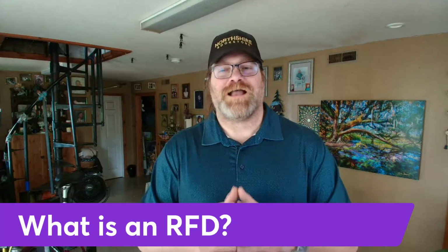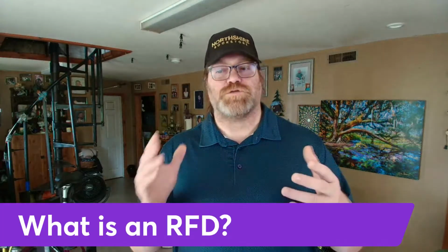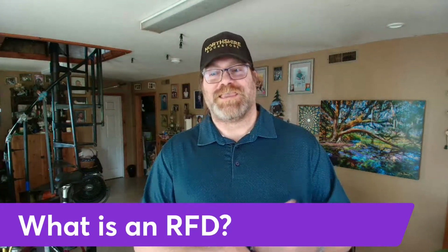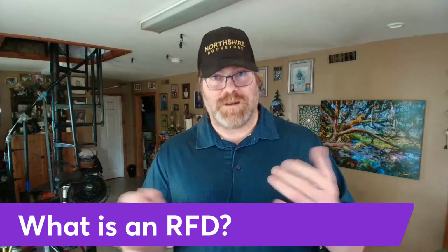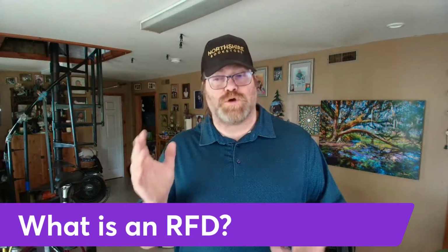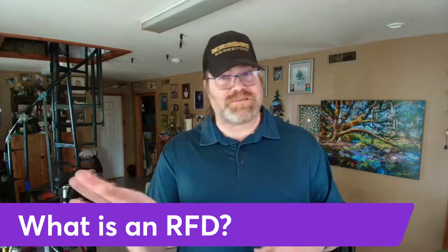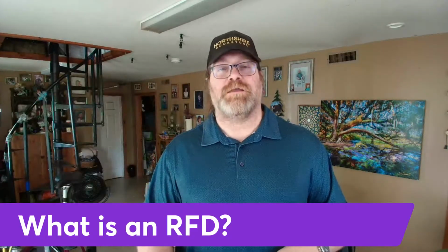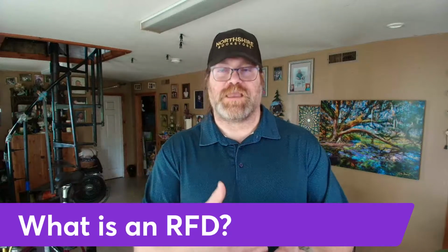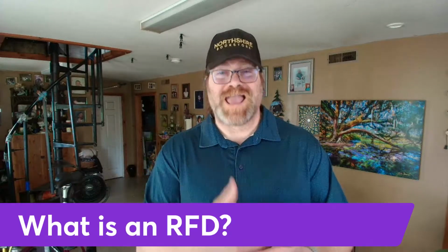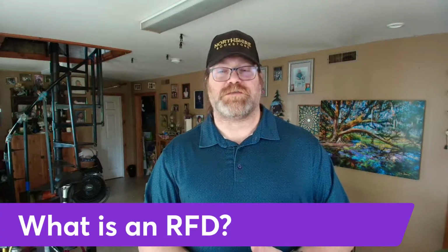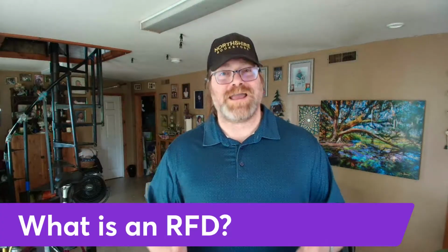So it's not simple. And so the first decision that you have to make is, is this even a combination product? Number one. You might not even have a combination product. So it would be nice to get that determination. It's not a combination product. Don't worry about it. But the people that are filling out their technical review, which happens in the first 15 days of receiving your 510K, they might not know that.